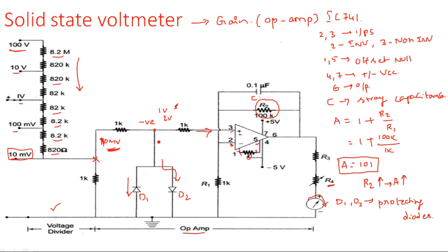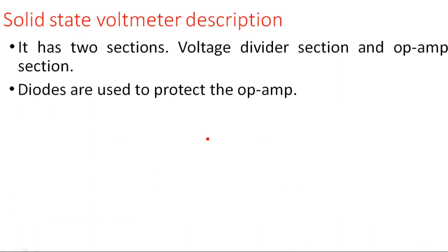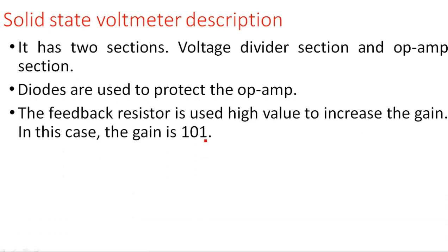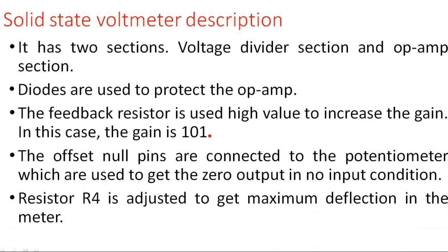So both diodes remain off under normal operation, and the operational amplifier functions normally. If extreme conditions like negative voltage or voltage exceeding the threshold occur, the diode turns on and protects the operational amplifier. To summarize: the solid-state voltmeter has two sections — voltage divider and op-amp. Diodes protect the op-amp, the feedback resistor sets the gain at 101, offset null pins with a potentiometer zero the output at no input, and R4 is adjusted for maximum deflection.